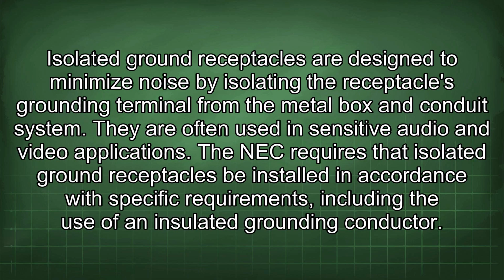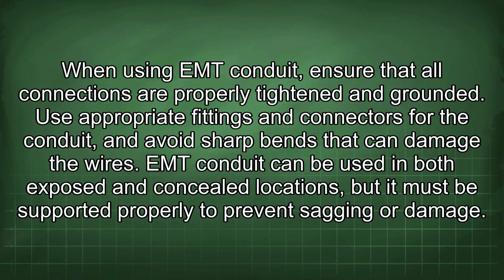Isolated ground receptacles are designed to minimize noise by isolating the receptacle's grounding terminal from the metal box and conduit system. They are often used in sensitive audio and video applications. The NEC requires that isolated ground receptacles be installed in accordance with specific requirements, including the use of an insulated grounding conductor. When using EMT conduit, ensure that all connections are properly tightened and grounded.